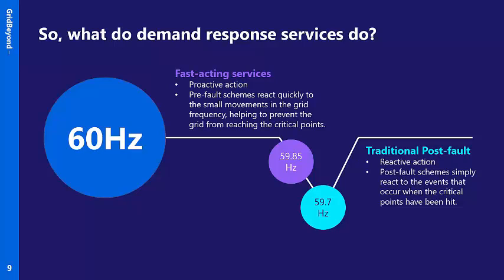Increasingly, as we put more and more renewable generation on the system, we get much more occurrences of deviations in frequency, and we get a much faster change in rates of frequency. So we get the rate of change of frequency, or ROCOF, for example, becomes a much bigger issue when we have intermittent generation like wind and solar. And that's simply because the changes in the generation profiles of those assets can happen much more quickly. So as I said, wind blows, slows down, changes, cloud cover comes over a huge, 10, 20, 30 megawatts or bigger solar farm, then that can create very fast drop-offs in supply, and that creates very quick frequency deviation.